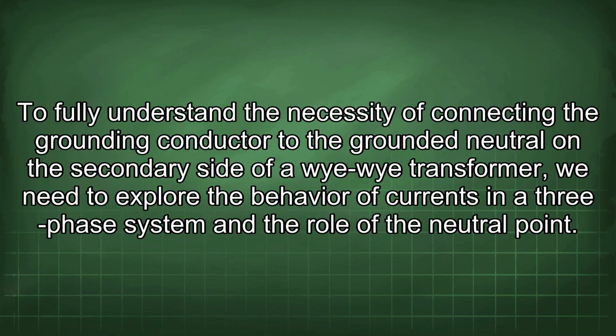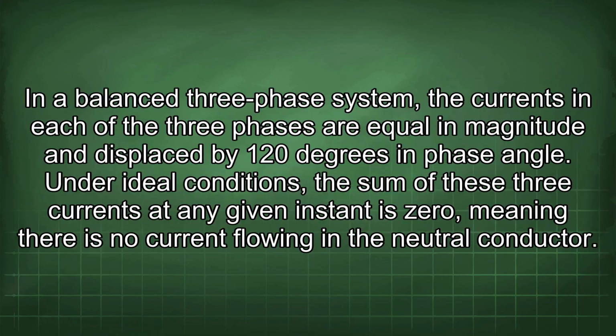To fully understand the necessity of connecting the grounding conductor to the grounded neutral on the secondary side of a Wye-Wye transformer, we need to explore the behavior of currents in a three-phase system and the role of the neutral point. In a balanced three-phase system, the currents in each of the three phases are equal in magnitude and displaced by 120 degrees in phase angle. Under ideal conditions, the sum of these three currents at any given instant is zero, meaning there is no current flowing in the neutral conductor.